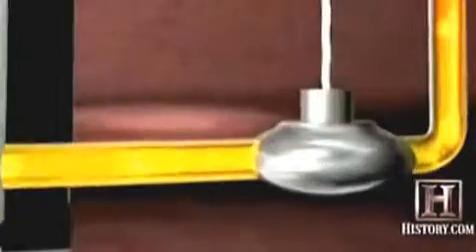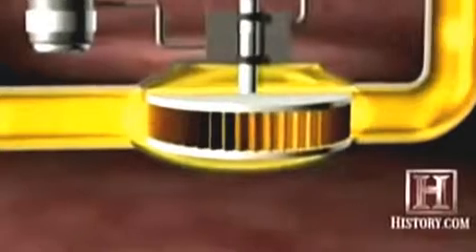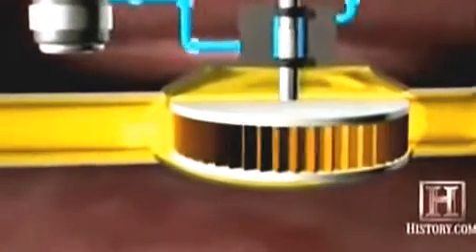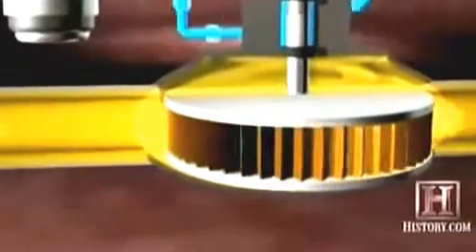with them. Because water couldn't be near the reactor, a chemical known as tetralin was used to cool the bearings in the pumps that circulated the sodium as it carried heat away from the fuel rods. Everything worked well until tetralin started leaking through cracks in the pump seals, and into the reactor.